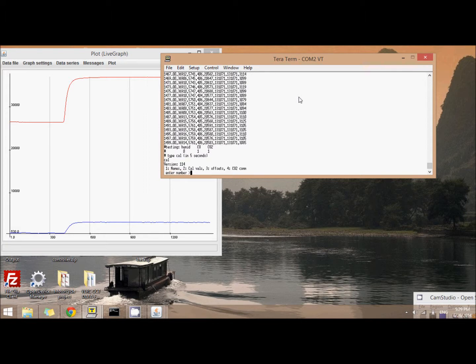If you do that in the first 5 seconds, that means we've entered into calibration mode, and you have these choices that you see here. We'll get into them more in detail after we process our CO data, but for right now, all we need to do is communicate with the CO2 sensor. So that's what I'm going to do. I'm going to enter 4 for CO2 communication. You see that's the last menu option there, and then it asks us for a command.